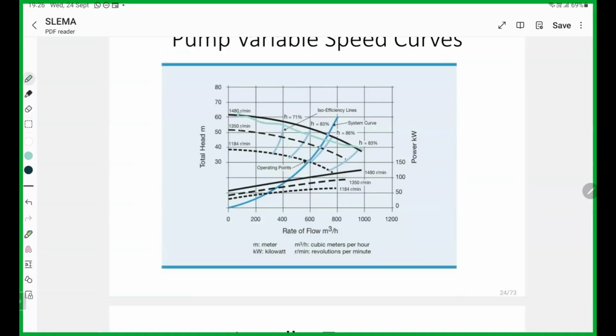Then we can change the pump curve by reducing the RPM, right? The general VFD drives. Then reduce this RPM, then your duty point you can change by VFD, right? The important thing is that your system is somewhere like this. People always think that if we use a VFD, then it is energy efficient. We cannot say that directly.